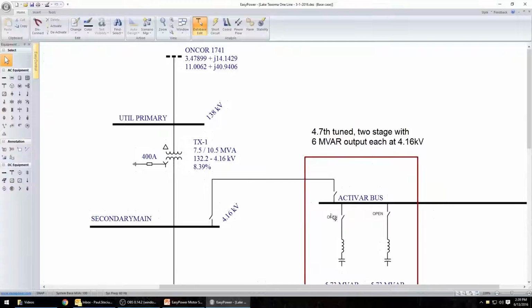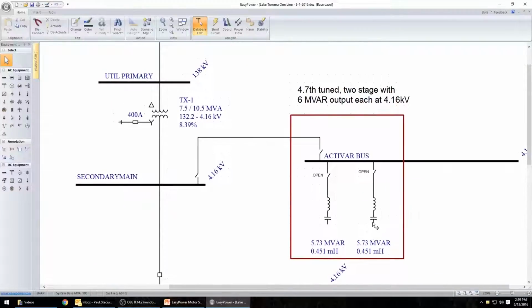This is the actiVAR bus, or the capacitor assist bus. This could very well be conventionally switched capacitors or a thyristor switched base system. This is actually two 6 megavar steps. When we apply an actiVAR to the system, we actually utilize detuned filters, something between the 4th and 5th harmonic. So these two 5.73 megavar stages actually represent 6 megavars output at 4.16 kV, and these were tuned to the 4.7th harmonic.